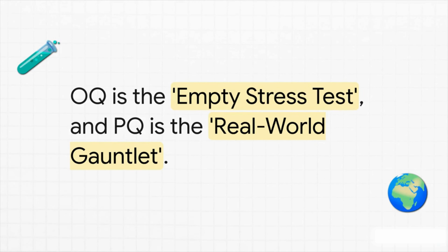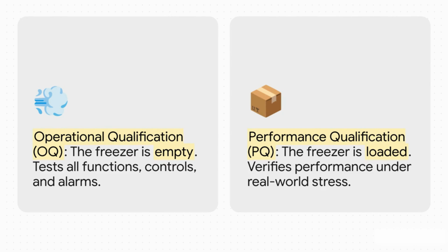Okay, let's move on to the next 2 stages and their analogies. Operational qualification, or OQ. That's the empty stress test. Then you have performance qualification, PQ, which is the real-world gauntlet. Now, they sound kind of similar, but the difference between them is absolutely critical. So OQ happens when the freezer is completely empty. You're testing every single function, every button, every alarm to make sure it works exactly like the manufacturer said it would. But PQ is the true test.